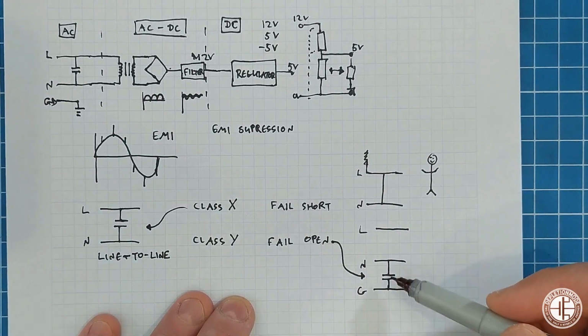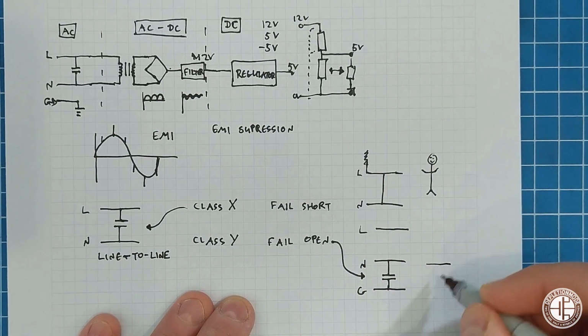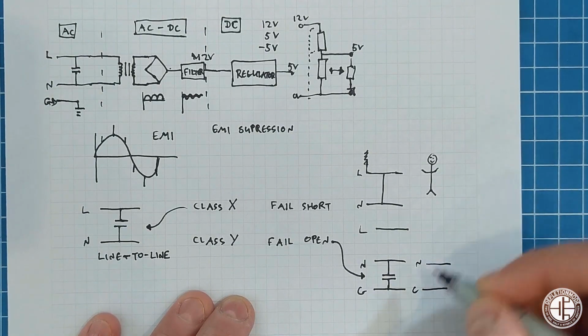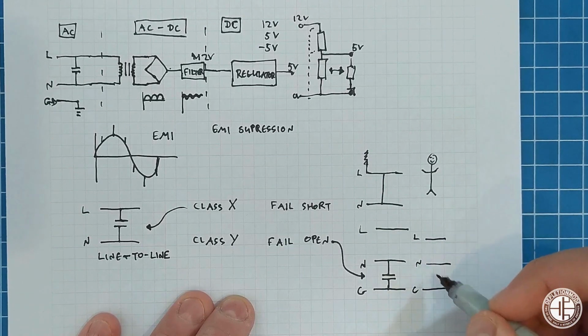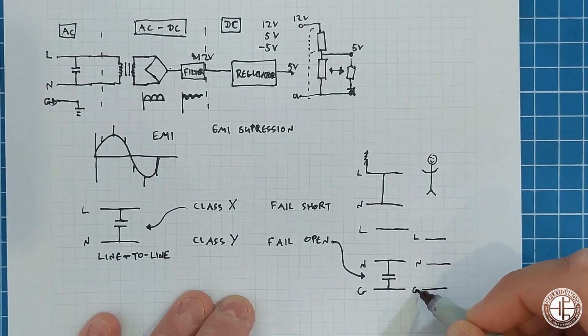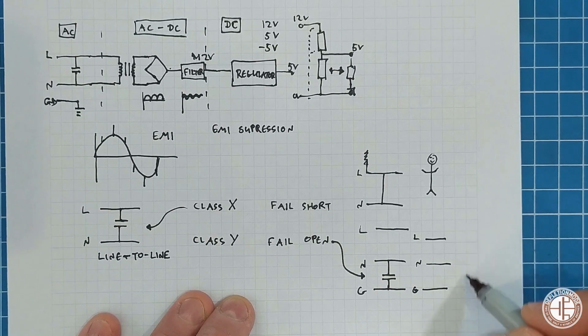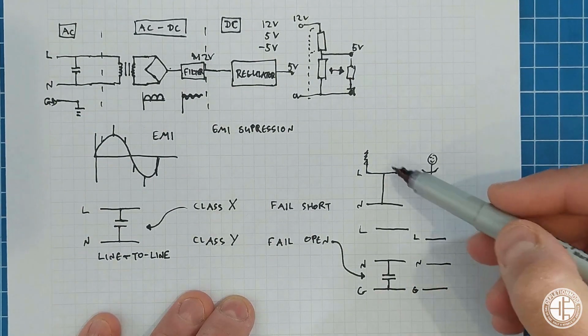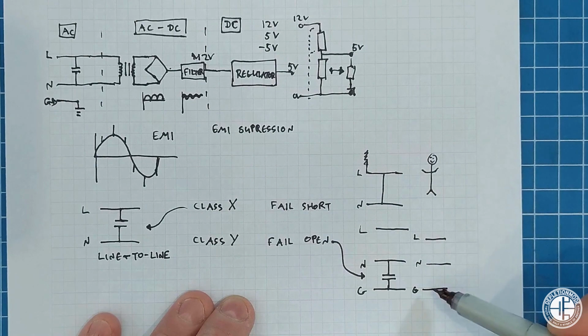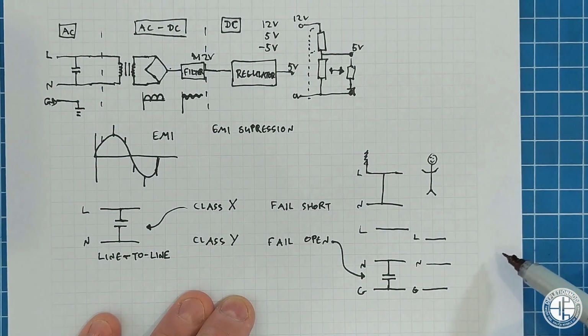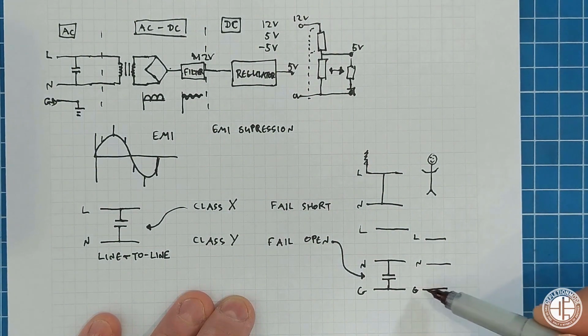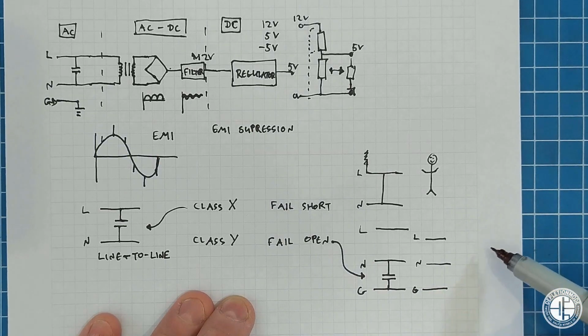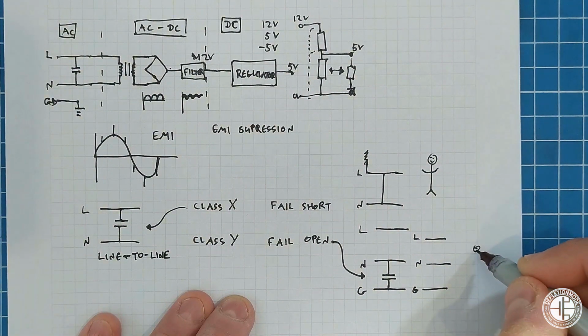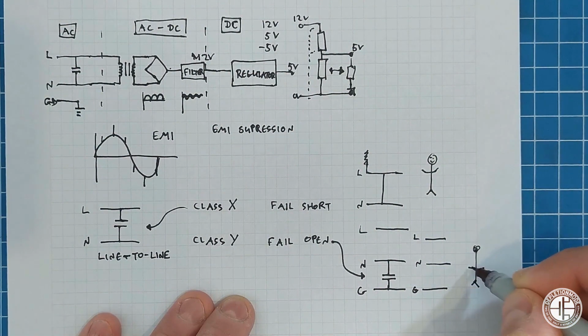Now, it fails open, meaning this thing blows up as if it's an open circuit between there. Why? Because your neutral, your ground, and your live here - you don't want to short circuit your neutral to your ground, because whatever protection the ground is giving in this part of the circuit would be lost. It's a similar reason to why you don't want a floating live. You don't want to disconnect the ground from the rest of the circuit. If you short out the neutral and the ground, you've in essence disconnected the ground from the rest of the circuit. So again, the idea is to keep you happy and alive.